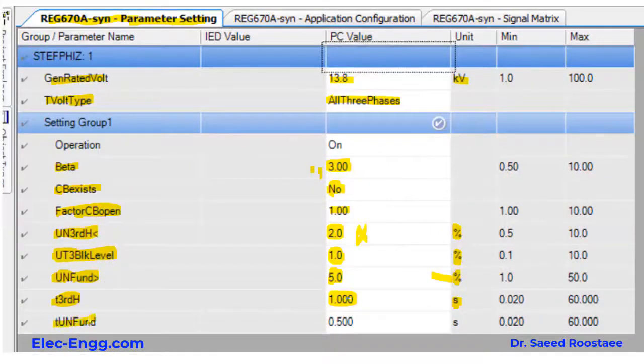Here we can set the trip delay in seconds for the fundamental frequency residual voltage. It is recommended to set this delay to 500 milliseconds if we don't have a GCB and two seconds when there is a GCB in the plant.